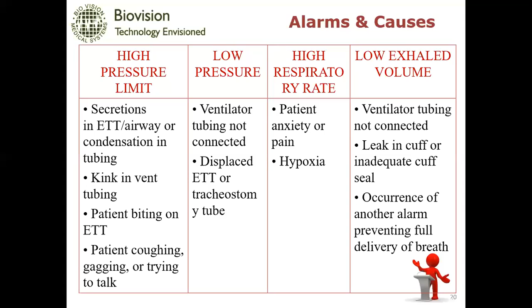So low pressure or low exhaled volume is very common when there is a disconnection. So whenever the patient is disconnected or there is a leak in the tubing, the patient circuit, there is a leak through the tubing with which you deliver the air. So in such cases, you get low pressure or low exhaled volume, basically. High respiratory rate: if the patient is over-triggering, you set the trigger, the patient is taking very shallow breaths, many number of shallow breaths, then you get high respiratory rate. If such is the case, you have to alter the sensitivity parameter.